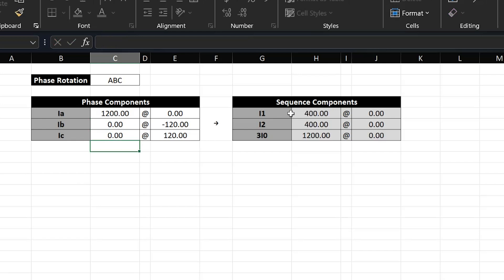The spreadsheet auto-calculates the sequence components on the right. You can see that the 3I0 current is equal to the A phase current, which is of course expected for a single line to ground fault on A phase on a radial feeder. So the 1200 amps for the A phase current and the 1200 amps for 3I0 match. We also calculated the positive sequence current I1 and the negative sequence current I2. Notice that for the zero sequence current I'm calculating 3I0 — three times the zero sequence current — not simply I0.